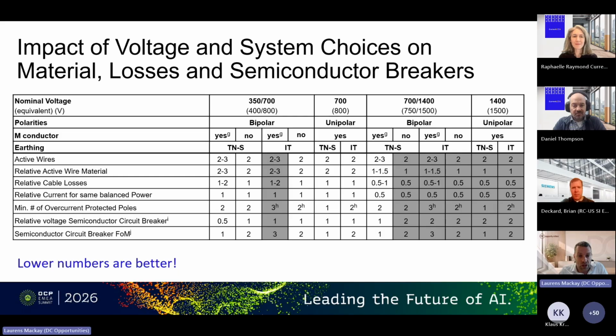Then next row is the currents. Very simple. Voltage goes up, current is half. And then we have the number of protected poles. And there's basically in some systems you need to protect more poles. In the bipolar system you need to protect at least 2 poles. In unipolar systems, if you do TNS grounding, you can also get away with protecting only one pole.